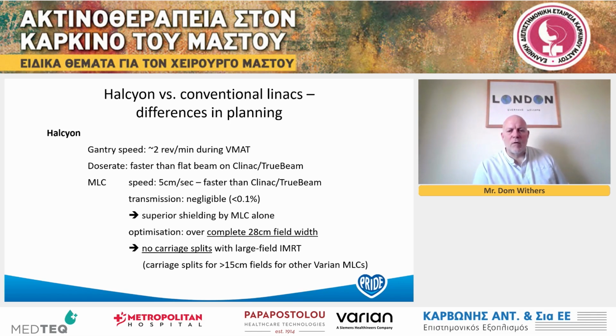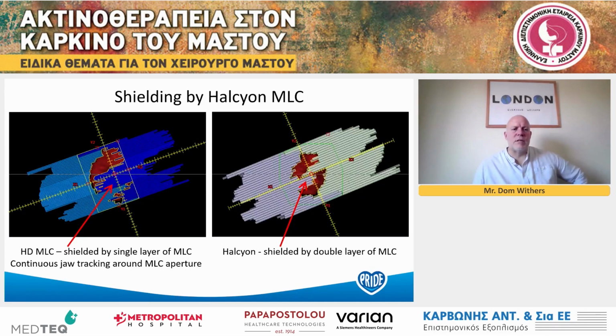So with typical Varian MLCs, there are carriage splits for IMRT, which means that there is a 15 centimeter window at which optimization is maximized and possible. And this window is really the same for VMAT as well. So for VMAT, we also have the complete 28 centimeter field width.